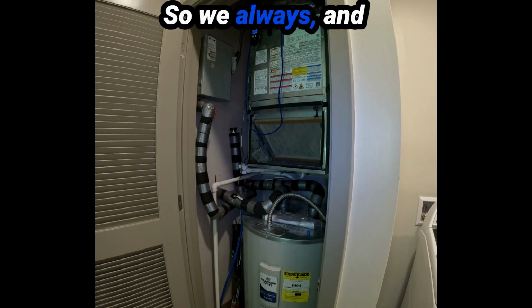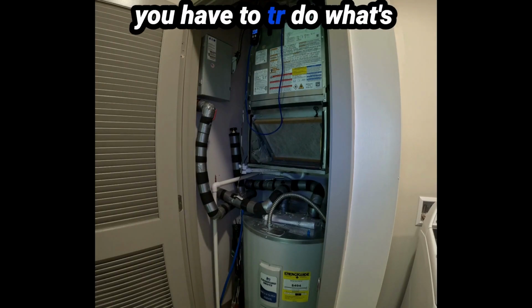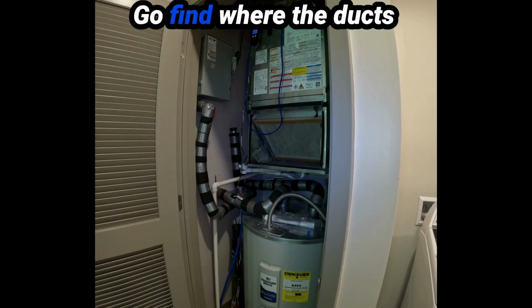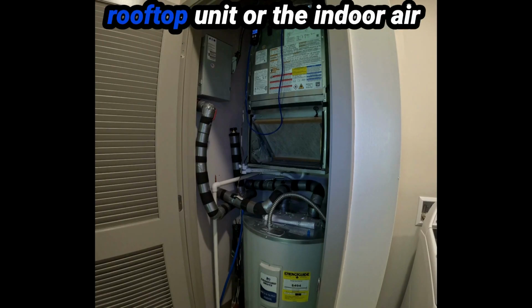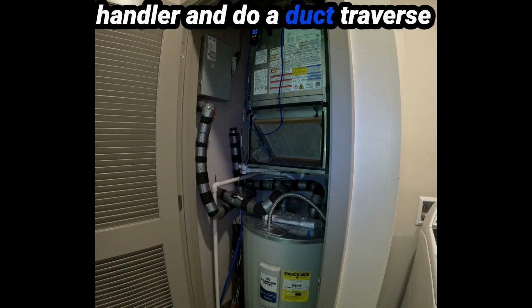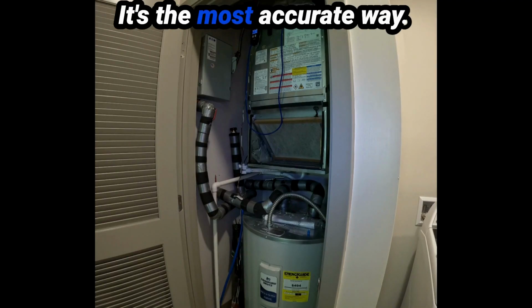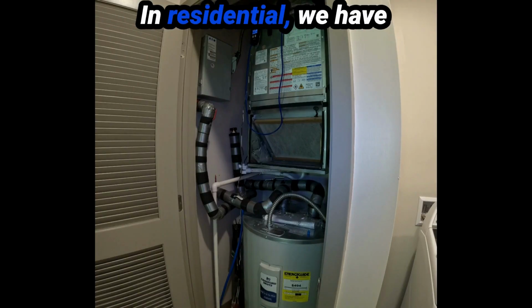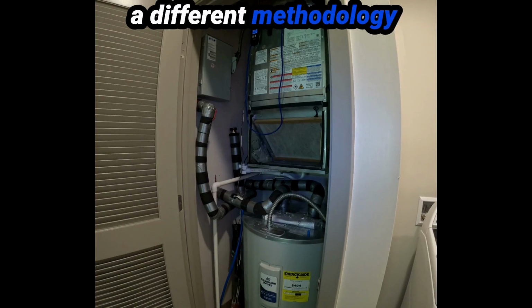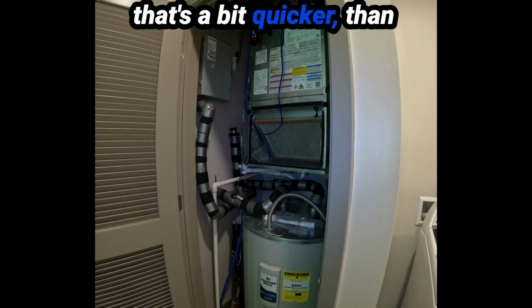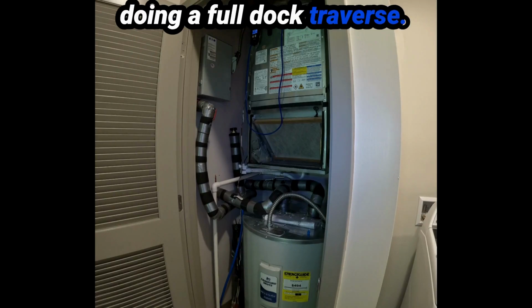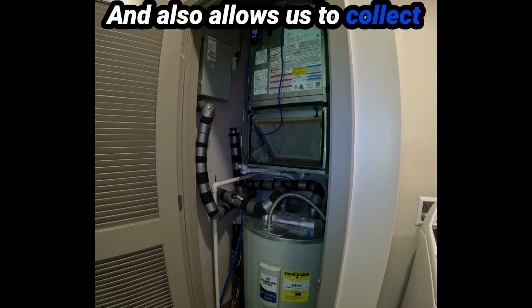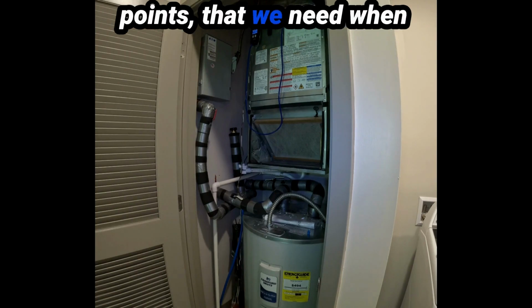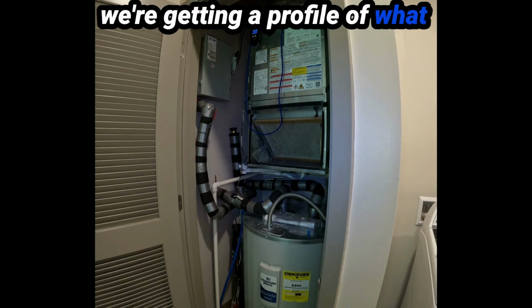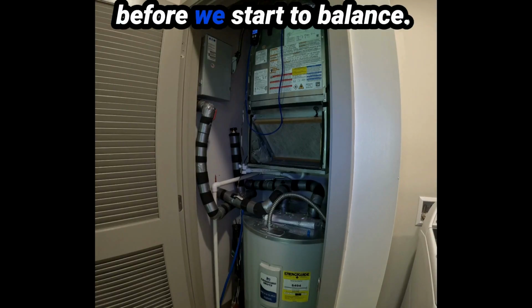So in commercial, a lot of times you have to do what's called a duct traverse. Go find where the duct's coming off of either the rooftop unit or the indoor air handler and do a duct traverse to get that total airflow. It's the most accurate way. In residential, we have a different methodology that's a bit quicker than doing a full duct traverse, and also allows us to collect our other pressure data points that we need when we're getting a profile of what the system's actually doing before we start the balance.